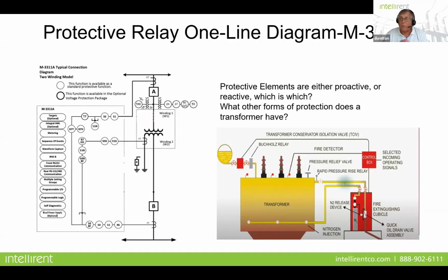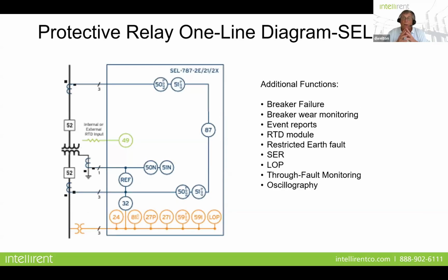So what other forms of protection does a transformer have? Well, we have Buchholz relays, pressure release valves, rapid pressure valves, different types of things, and fire extinguishing cubicles. If something should happen to the transformer, these items would take the transformer out of service to prevent further damage or catastrophic damage.